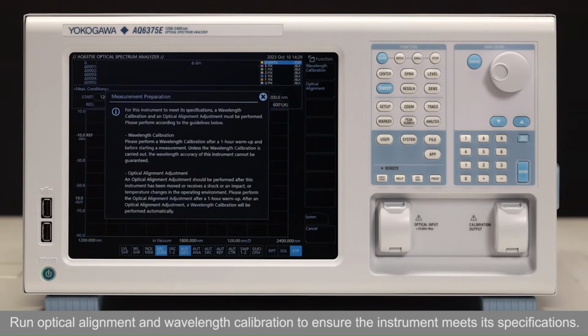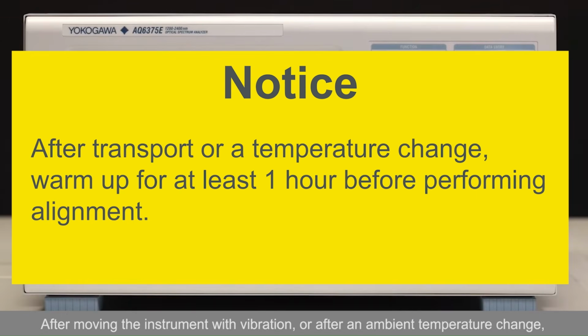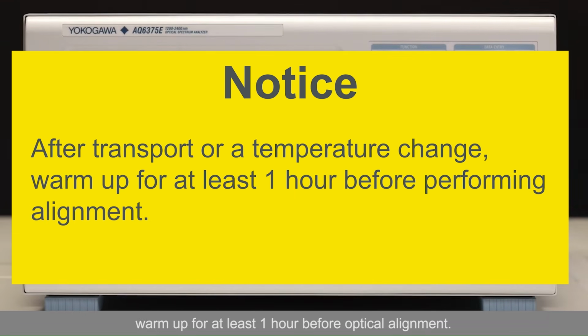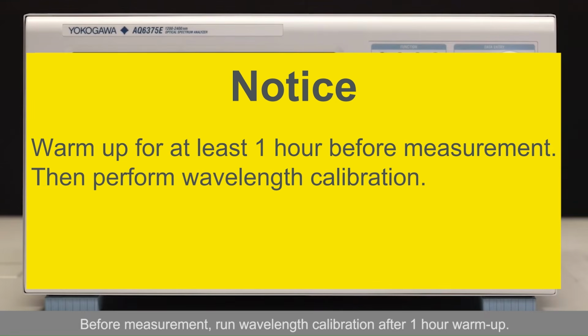Run optical alignment and wavelength calibration to ensure the instrument meets its specifications. After moving the instrument, or after an ambient temperature change, let the device rest for at least 1 hour before optical alignment. Before you start your first measurement, run the wavelength calibration.